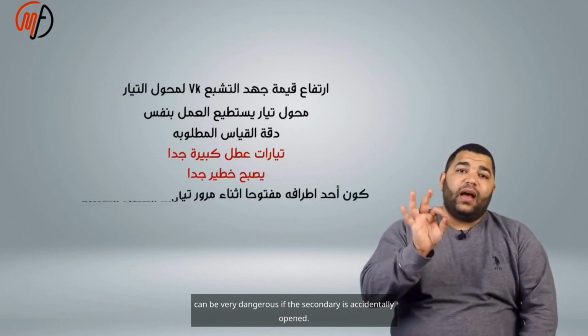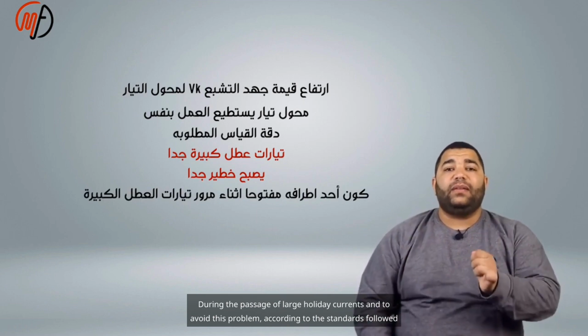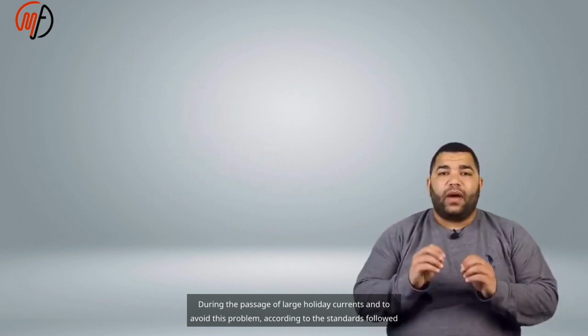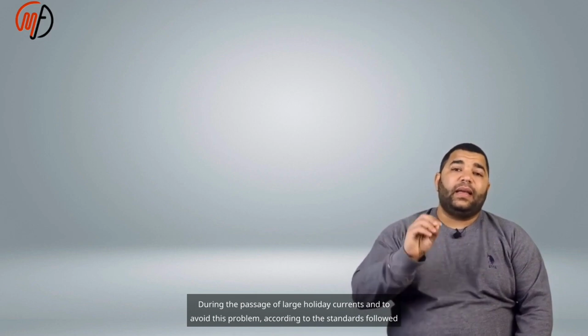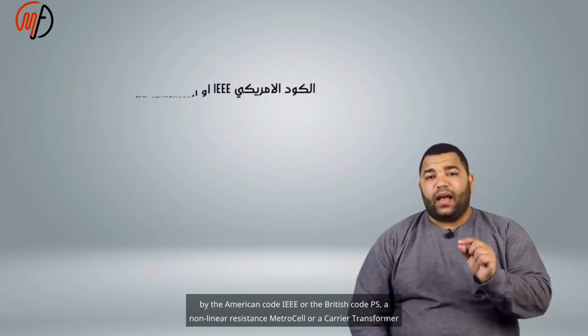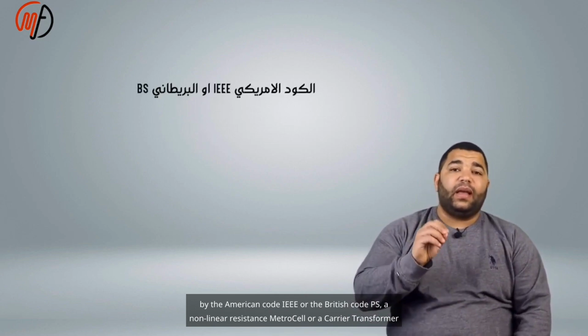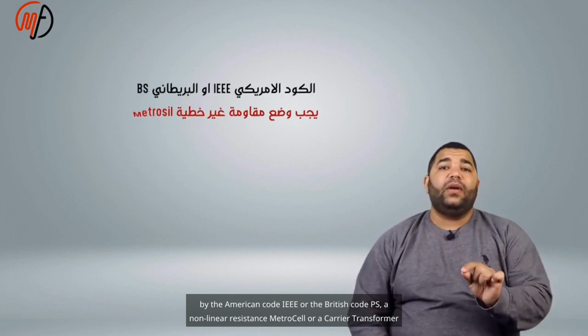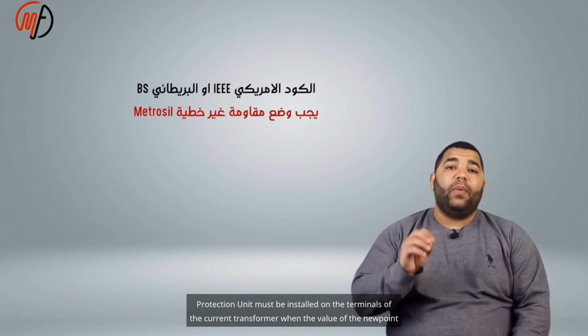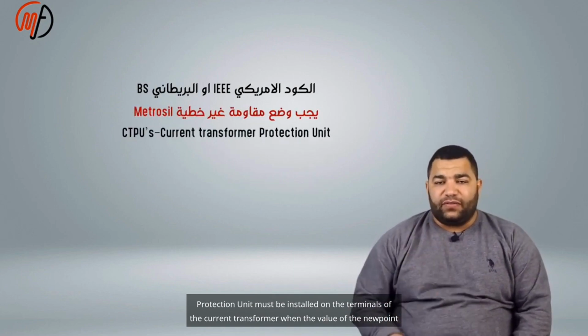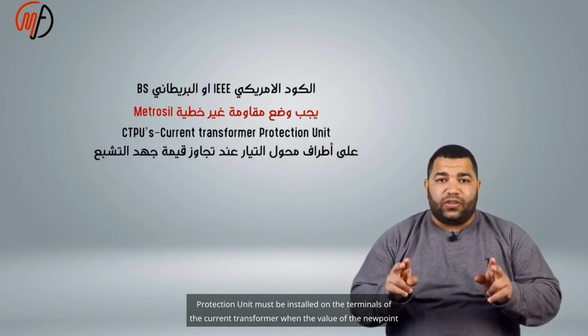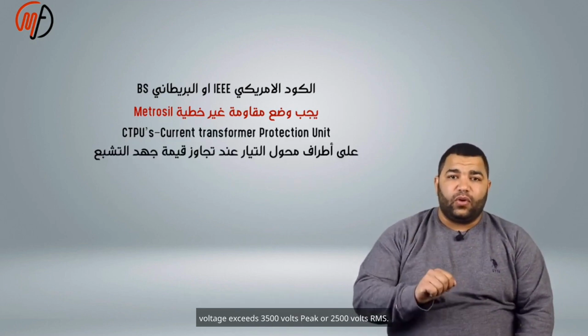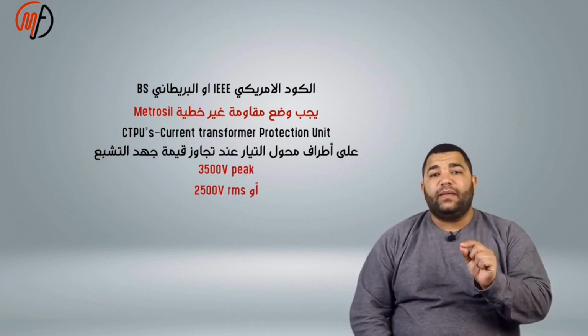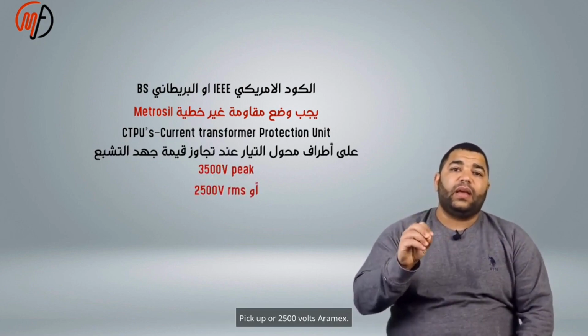During the passage of large fault currents, and to avoid this problem, according to the standards followed by the American code IEEE or the British code BS, a nonlinear resistance Metrosil or a current transformer protection unit must be installed on the terminals of the current transformer when the value of the knee point voltage exceeds 3500 volts peak or 2500 volts RMS.